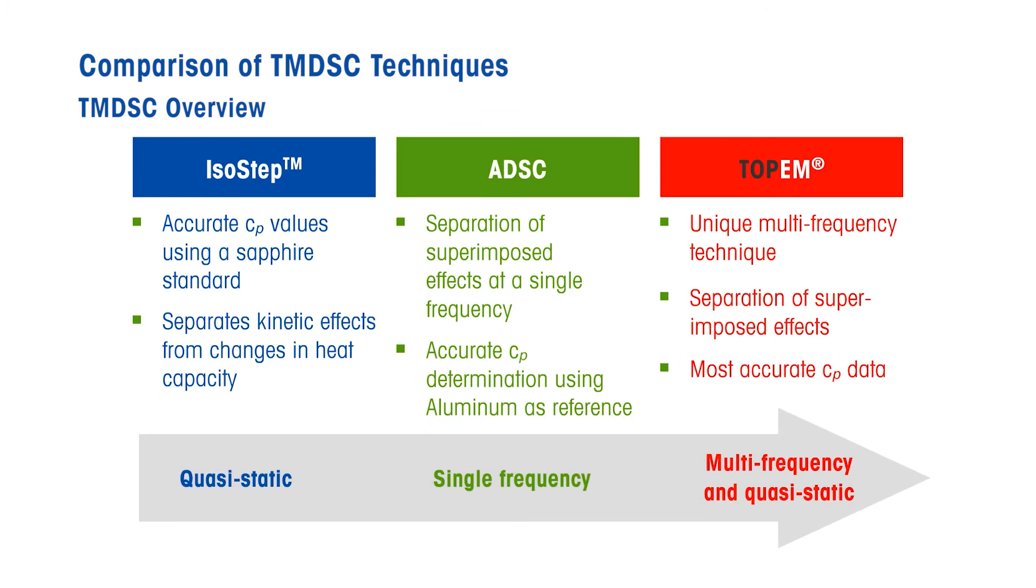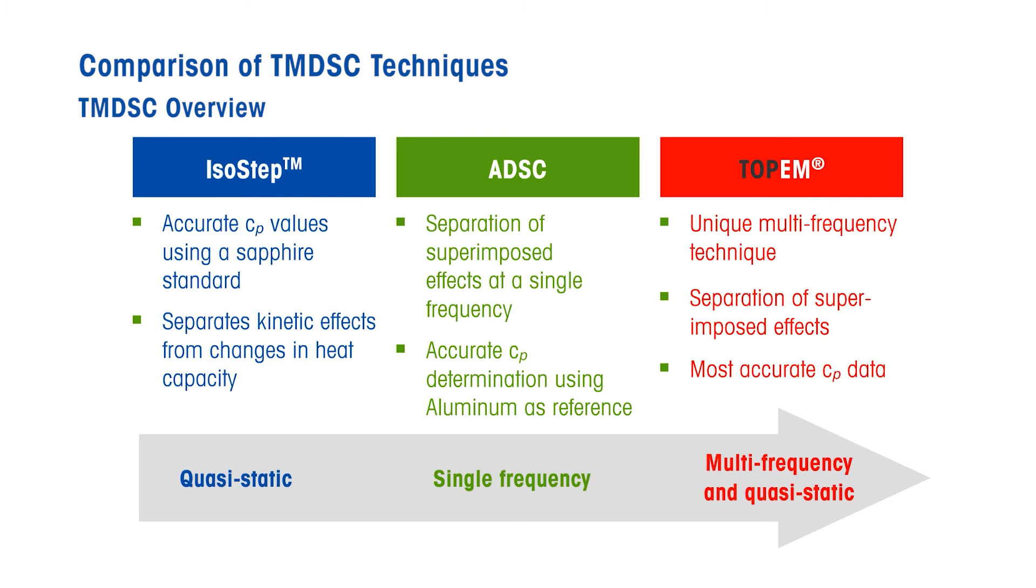All three techniques permit overlapping effects to be distinguished. This is achieved by separating heat flow into reversing and non-reversing heat flow components. In ADSC, different overlapping effects can be separated from one another at a single frequency. As a result, ADSC yields new information not obtained by conventional DSC, which allows you to understand and interpret the different thermal events that occur in the sample. Moreover, ADSC provides highly accurate heat capacity values using aluminum as a reference. IsoStep and TOPEM are explained in separate videos.